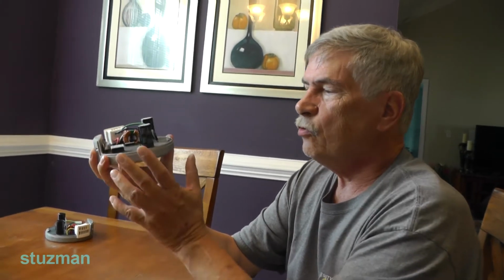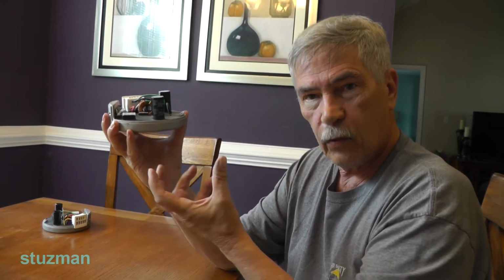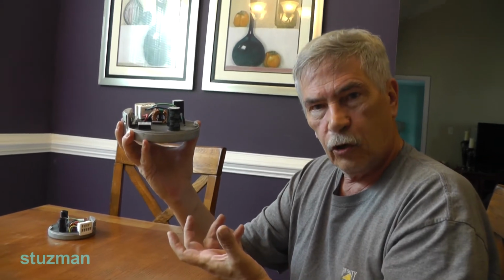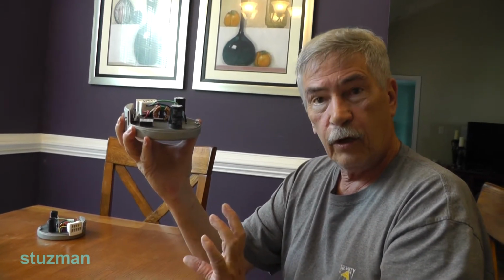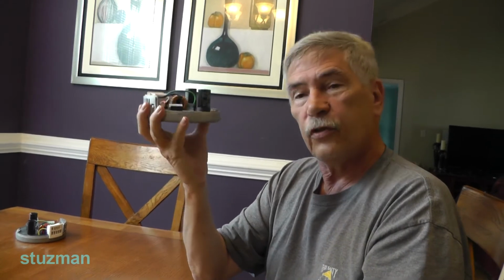So what happens is the unit will start the motor up, run it in one direction, then it's going to look at the current. If you have airflow, your current's going to be up. Then it will turn around and reverse the motor, and with no airflow, you're going to have very little current. At this point, somehow the board will program itself to that rotation. So it's quite possible that when we put this unit in, this motor may run backwards because it was basically programmed to the other one - it programmed itself to the other unit. See what I'm saying? Which won't help us.